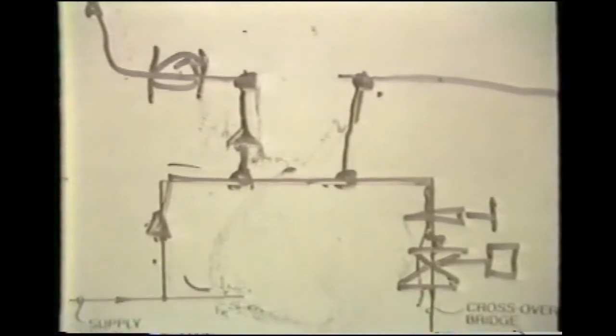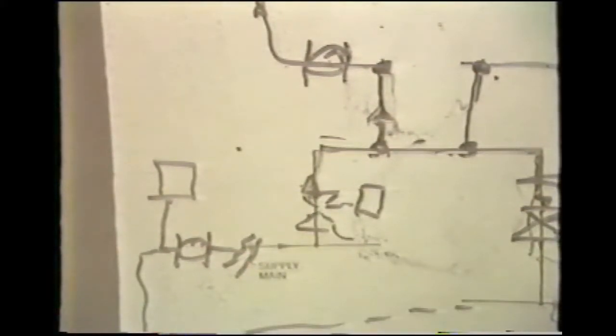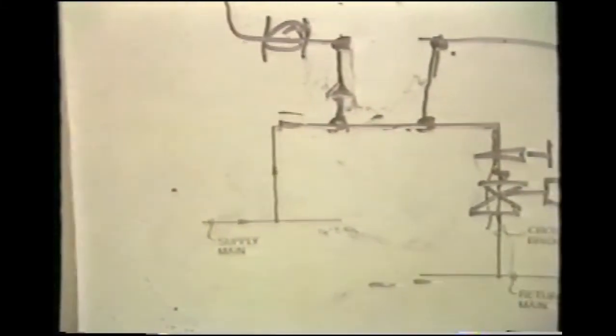We have the control valve in the return line. The pressure developed by the primary pump and its compression tank will be delivered directly into the secondary circuit, so we'll operate at a fairly high static pressure. Conversely, if that control valve were changed to the supply side, we would back pressure from the compression tank and into the secondary circuit through the return line so that our static pressure in the secondary circuit itself would become much lower. But the conventional arrangement is to apply the two-way valve in the crossover bridge.